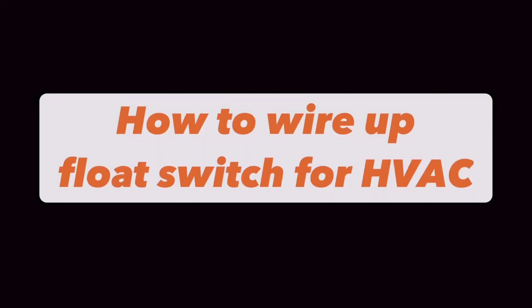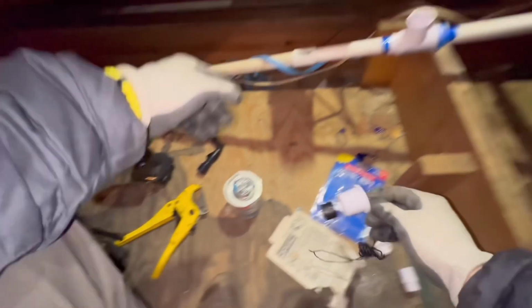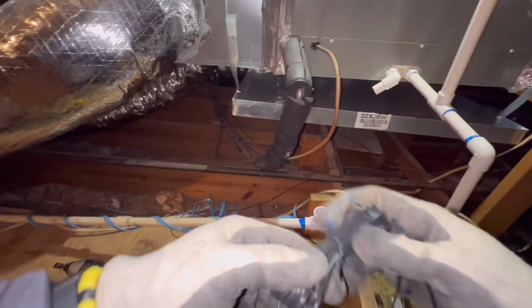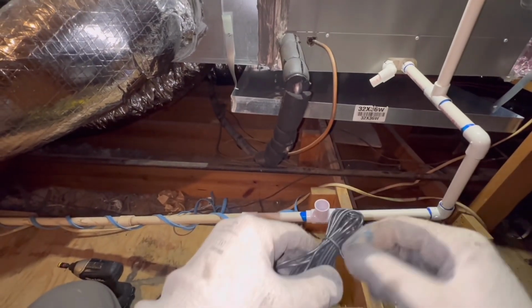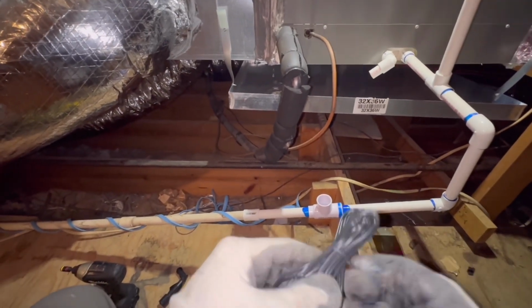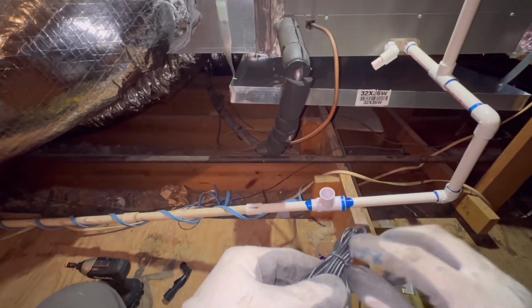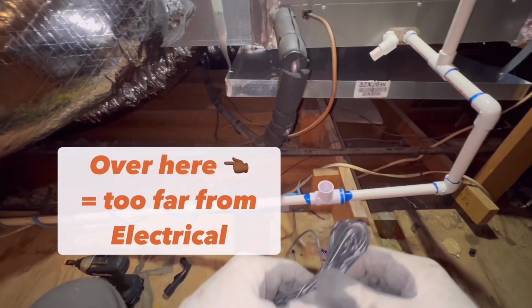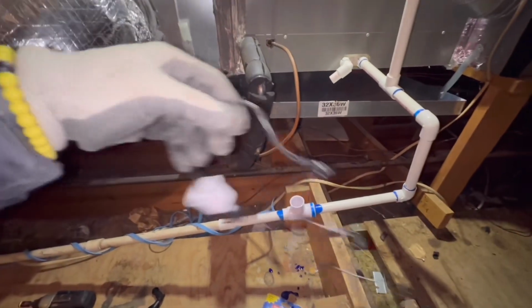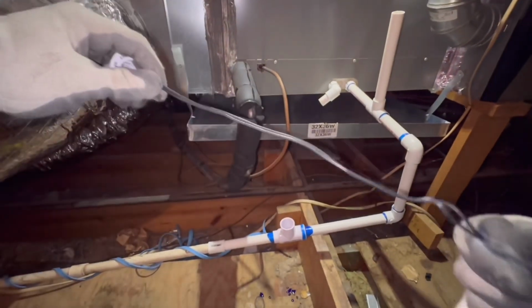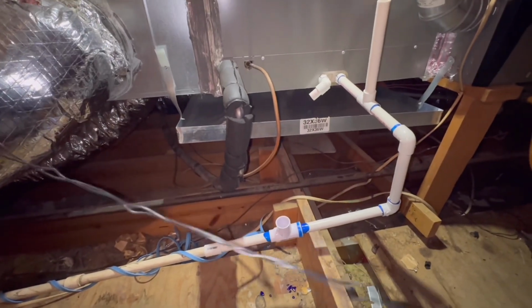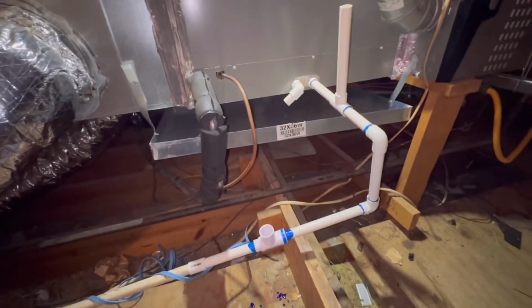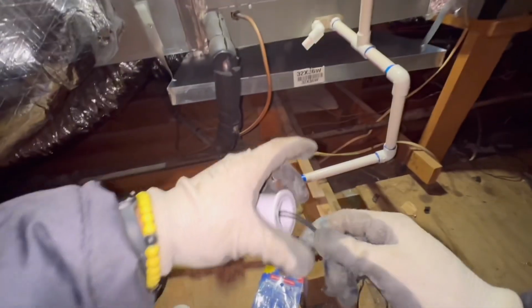The next step is how to wire up the float switch for your HVAC system. It is important that I mention when selecting the location in the primary drain line, you might want to make sure that the wires reach over to the electrical section. This one actually cut it pretty close. If you're following along while you're installing this, make sure your wires reach to the electrical section of your furnace or air handler.